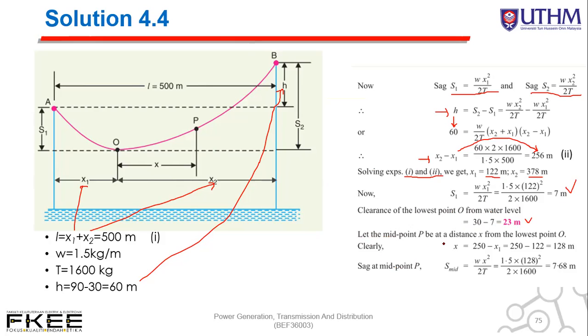Then let the midpoint P be at a distance X from the lowest point O. So we can calculate X equal to 250 minus X1. So we get X equal to 128 meter. Then we can calculate the sag at midpoint, Wx square divided by 2T, and we get 7.68 meter. All right. So this is 122 meter for X1, and 378 meter for X2, 7 meter for sag S1, 23 meter is the clearance, 128 meter is the distance X between O and P, and the clearance of midpoint P from water level is 23 meter plus 7.68 equal to 30.68 meter. All right.